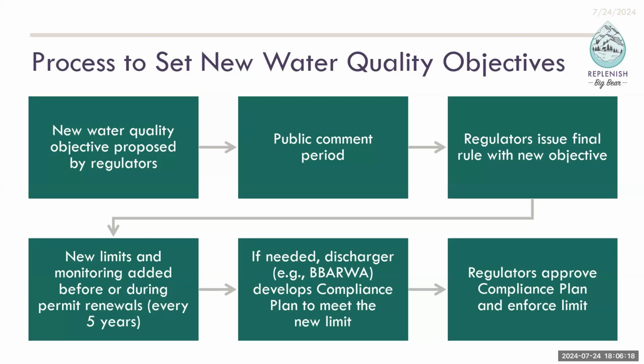Thankfully, with the process we have here, we have pretty high confidence with pretty much all the CECs and pharmaceuticals and forever chemicals that are out there. We're already going to... The forever chemicals we did test for were all non-detect. Right? Yeah. So for the ones we already tested, we're already non-detect, but you do have some time to be able to meet the objectives and get to that point. And that's consistent across the state, because there are a lot of agencies that can't meet objectives that come out, so they have to be given some time to maybe construct a new process or change operations.